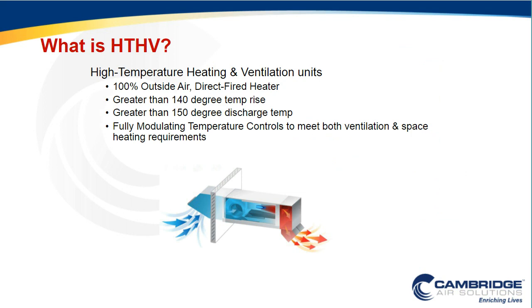So again, for those on the call, we are here to talk about a technology called HTHV, or high temperature heating and ventilation units. For those that have not been in the large warehouse, distribution, or industrial space, this may be a new technology for you. But what is HTHV? Well, HTHV, as defined by the industry, is a 100% outside air direct fired heater with performance criteria of greater than 140 degree temperature rise and greater than 150 degree discharge temperature. Those key temperature and discharge temperature figures are what make it high temperature heating. And then we qualify the ventilation units in that this system has fully modulating temperature controls to meet both our ventilation and our space heating requirements. So this, in a nutshell, is the performance criteria for HTHV, and we'll talk in depth about how that impacts the sizing, the deployments, and ultimately the energy efficiency of heating high bay manufacturing, warehouse, and fulfillment centers.